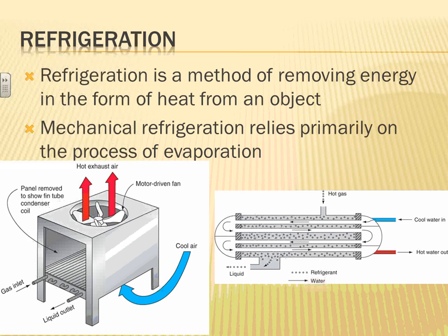So the refrigeration cycle, guys, the reason why we care about the refrigeration cycle is that in the NEC code book, if you have a piece of equipment that has some type of compressor on it, the NEC treats this particular motor differently than any other motor and assigns a standalone article for it, which is article 440, where the calculation is slightly different, not a whole lot different, but slightly different. That's why we care about the refrigeration cycle.